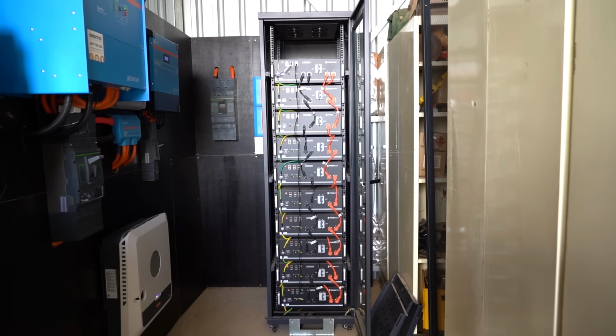We've done a bit of DC coupled charging and a bit of AC coupled charging with a big 15 kVA Quattro. Our customer's got a lot of large loads in his house, so he's got a Tesla charger, underfloor heating and heat pumps for hot water, air conditioning, and all the other electrical needs inside the house. We wanted to go the big unit so we've got a lot of surge capacity, and we've teed it in nicely with a bit of AC coupled charging to take some of the load off during the day.